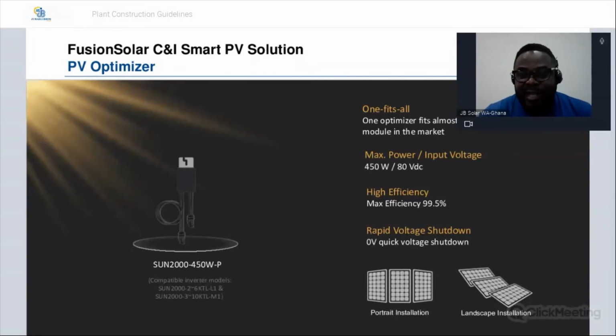Again, the optimizers are only applicable to panels up to 450 watts with the current Huawei optimizer models. If the panel capacity is above 450 watts, you cannot use these optimizers. I always like to highlight the limitations so you don't end up purchasing something that won't work for your system, leaving it as if we hadn't informed you properly.